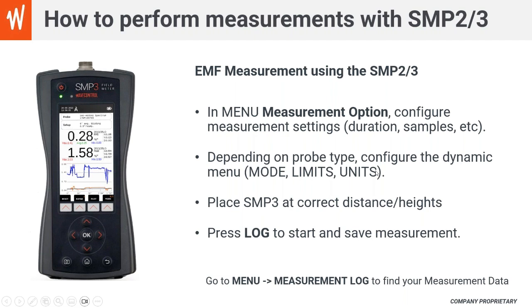And then once this is done, you just need to place the SMP meter at the correct distance and the correct height, as specified by your standard, or depending on the application which you want to measure. So take into account the distance of the operator from the machine, which has to be measured. Then once you set the device at that point, just press the LOG button to start the measurement and then save the measurement. These measurements are saved to your device, and then you can access the results from the measurement log.